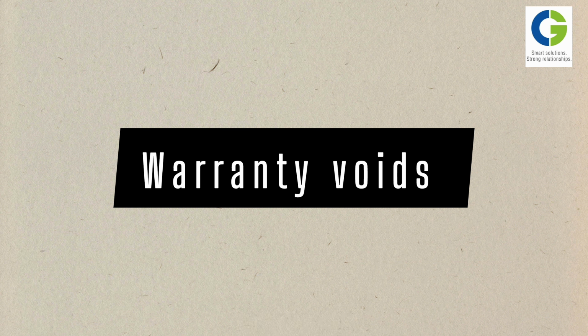Warranty guidelines. The warranty will not be applicable if the pump is used for the wrong application, such as handling solid rocks, chemicals, ceramic powder paste, mud, or cloth. It also does not apply if the pump is installed with incorrect mounting, with no use of a float switch or improper float installation, if an incorrect extension cable size is used, if the pump runs without water in the sump or tank, or if water or any coolant is filled inside the motor.